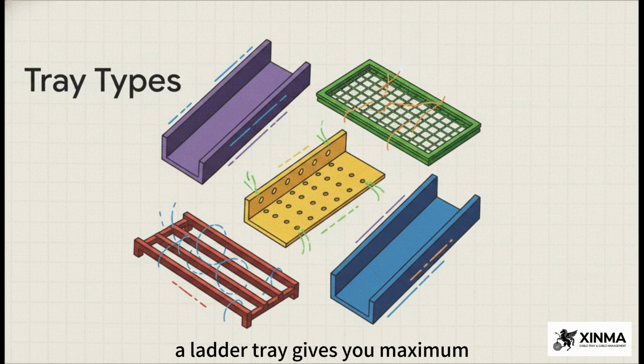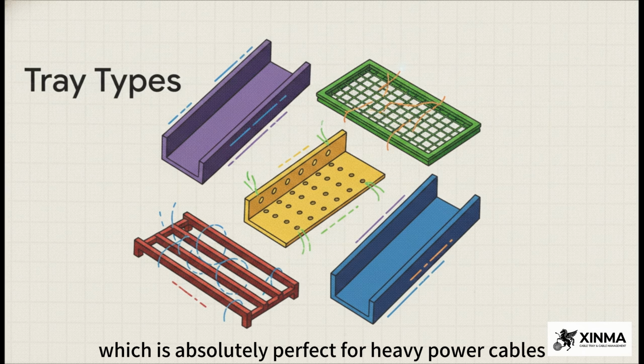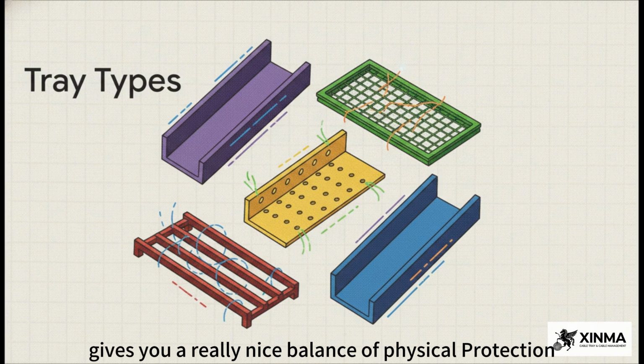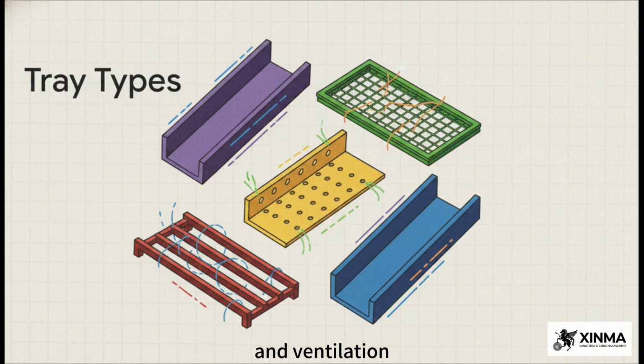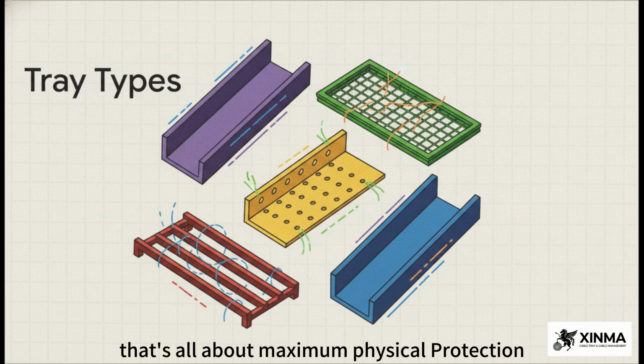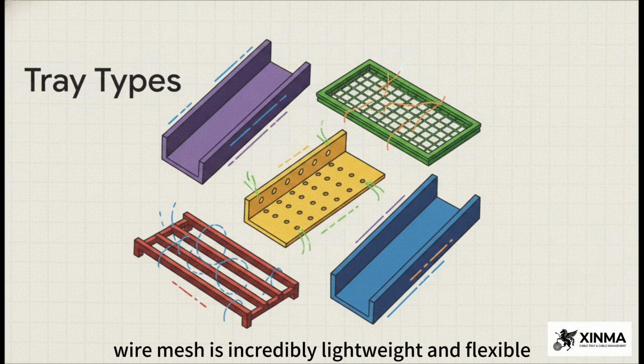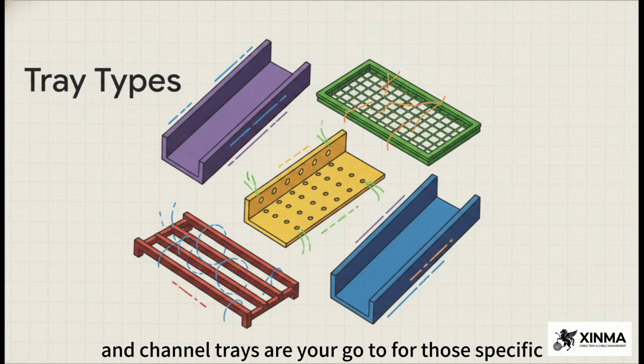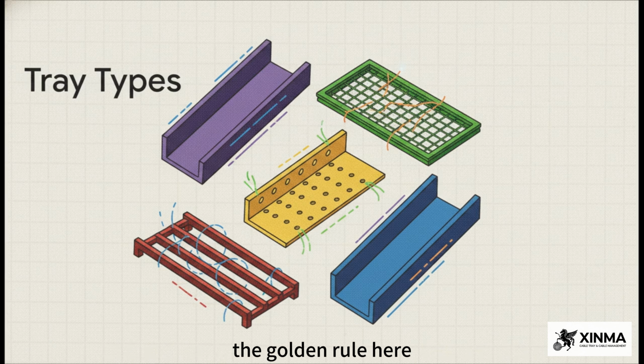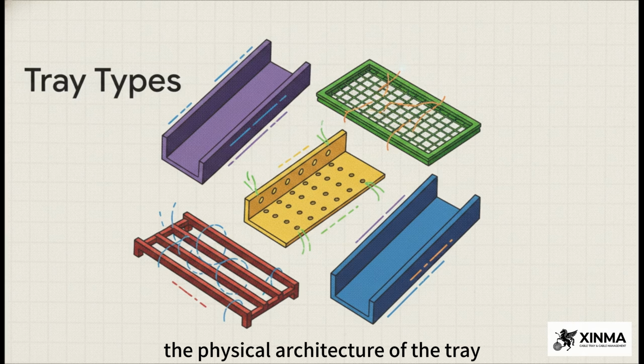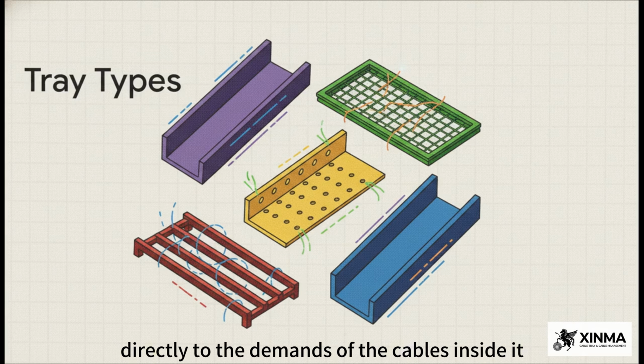A ladder tray gives you maximum airflow and high weight capacity, which is absolutely perfect for heavy power cables. A perforated tray gives you a really nice balance of physical protection and ventilation. Solid bottom is all about maximum physical protection. Meanwhile, wire mesh is incredibly lightweight and flexible, and channel trays are your go-to for those specific smaller cable runs. The golden rule here is that you have to match the physical architecture of the tray directly to the demands of the cables inside it.